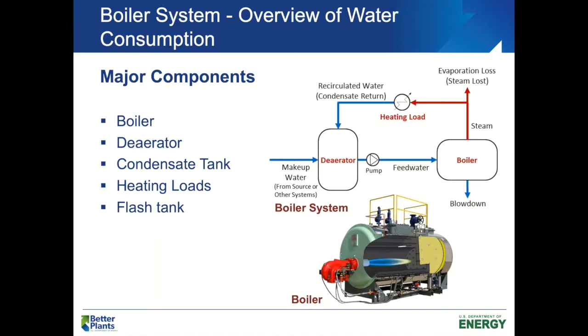So moving to some of the opportunities in the system, the first one is very similar to the cooling towers. It's minimizing blowdown and optimizing the cycles of concentration. And all the points we discussed for the cooling tower also apply for boilers in this case. The second one is with respect to increasing condensate return. And this is a big opportunity that exists in your boiler and steam system, right?